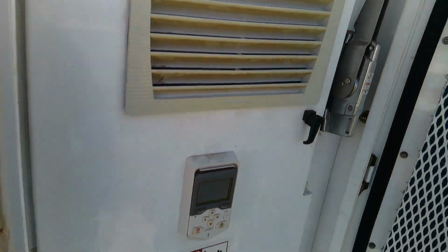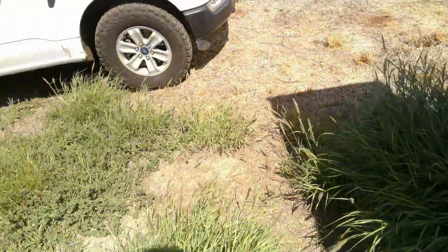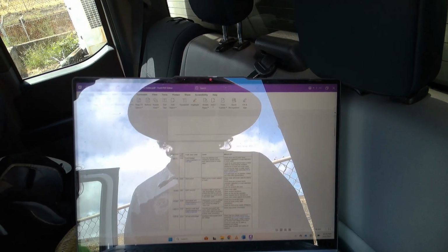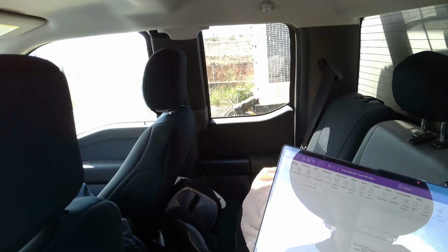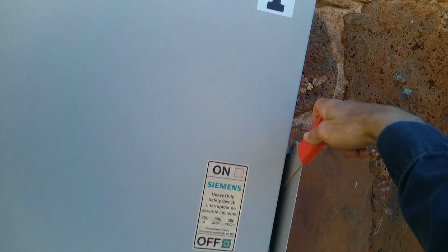Let's look that up in the ACS 580 manual and see what it says. "In motor or motor cables, by measuring the insulation. Try running the motor in scalar mode if allowed. If no earth fault can be detected, contact your local ABB." Earth fault. So basically it's saying there's an earth fault somewhere.